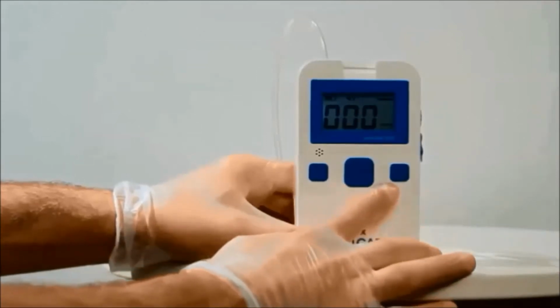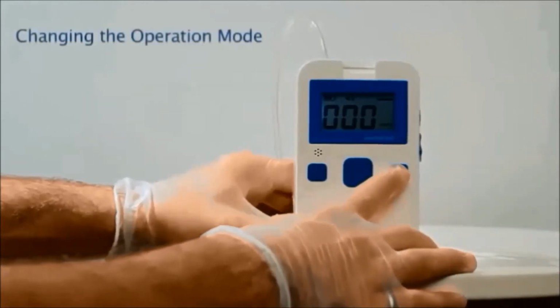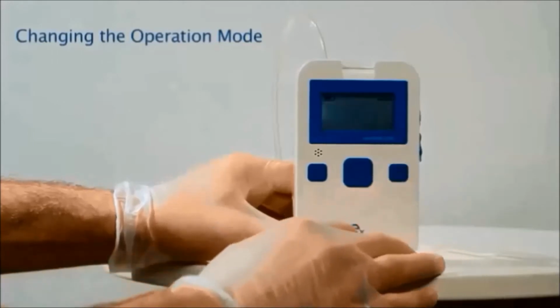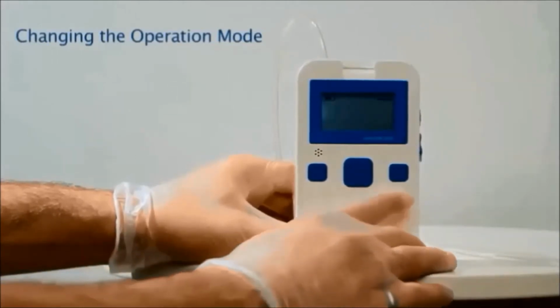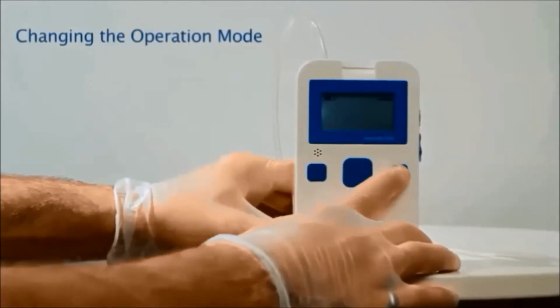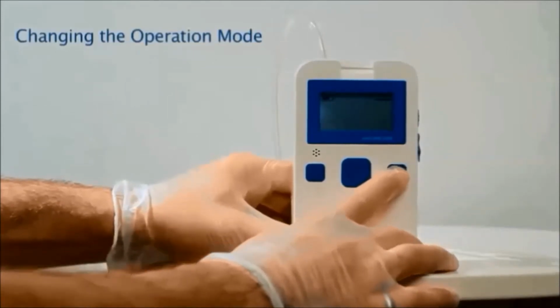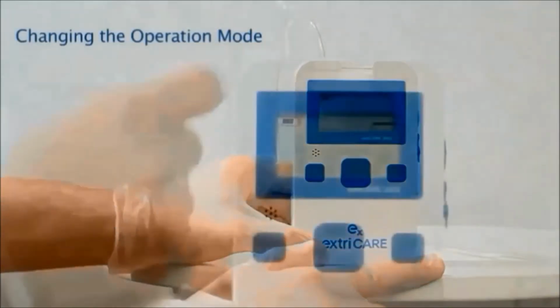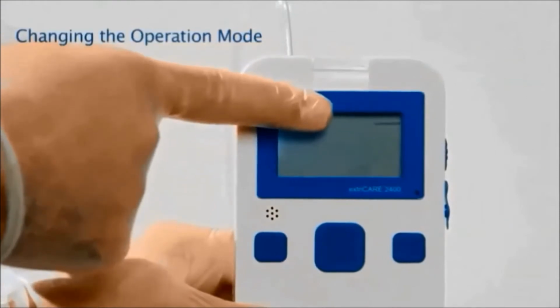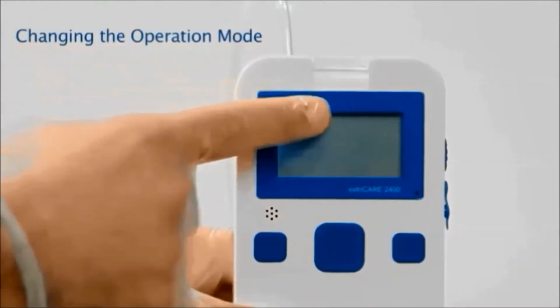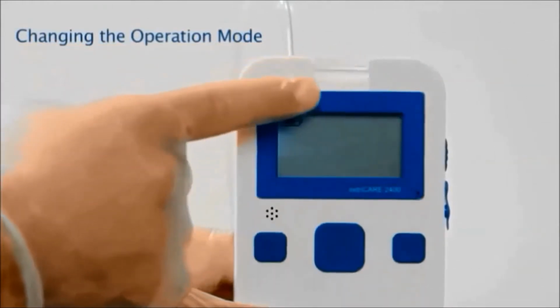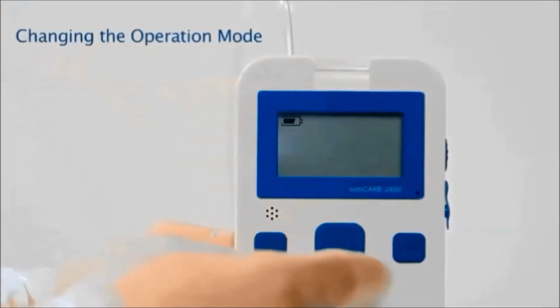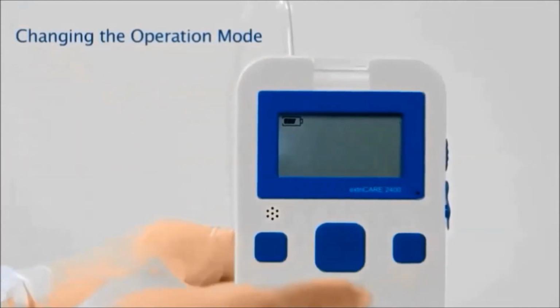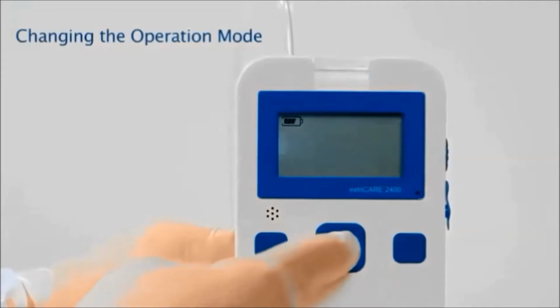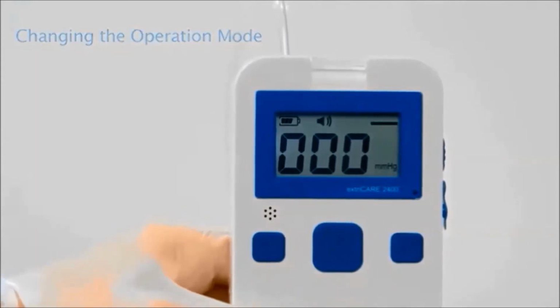To change the operating mode, hold down the mode button until you hear a beep. After the beep, press the mode button to change between continuous and intermittent mode. In the top right corner of the screen, you'll see a straight line indicating continuous mode or a dotted line indicating intermittent mode. Once the desired mode is selected, press the Pump button to confirm.